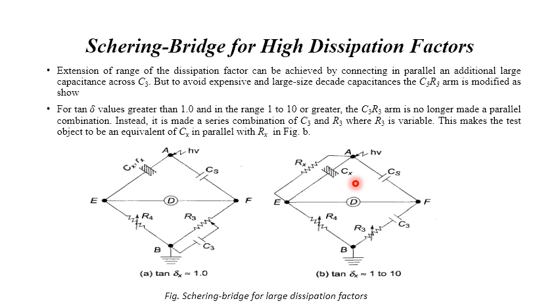Under this condition, we know that the opposite arms multiplied are equal: Cs and R4 multiplied is equal to Cx, Rx, and the R3 and C3 values. So this makes the test object Cx in parallel with Rx, a better approximation for the capacitance and the dielectric. With this modification, the tan delta range is made wider, varying from 10 to the power of minus 4 to values even greater than 10. So this arrangement we showed here is for 1 to 10, and the earlier one is for 1, for the loss angle measurement.